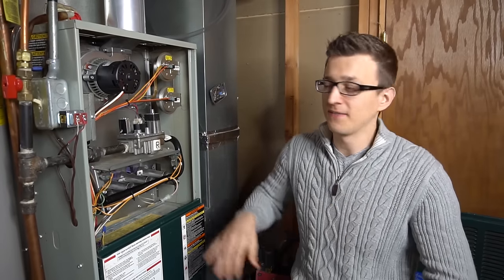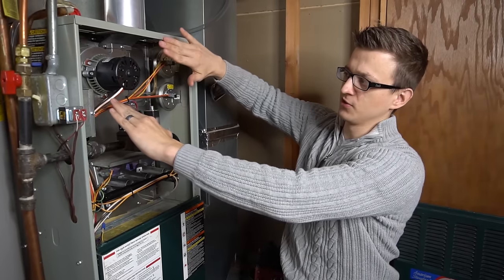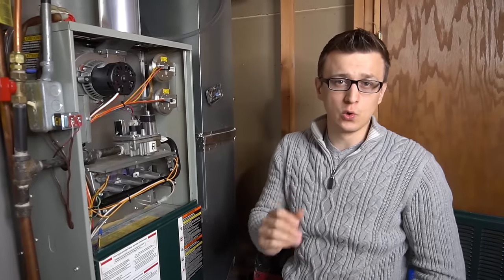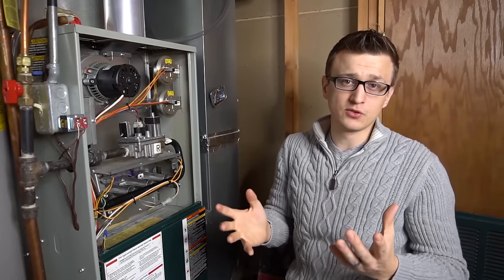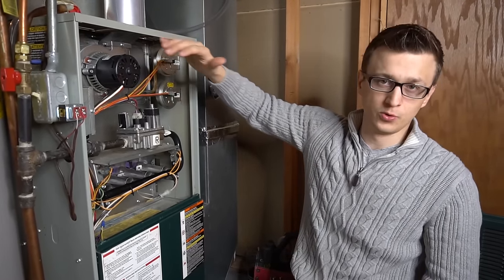One last thing I want to mention: if you have a really old furnace that's natural draft, usually you'll have some scoops right here. Those older furnaces will not have an inducer motor. If something's wrong with the chimney and the exhaust fumes are coming back out through those scoops, that can be really dangerous as well.